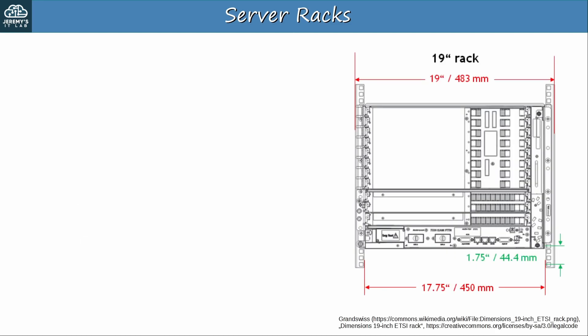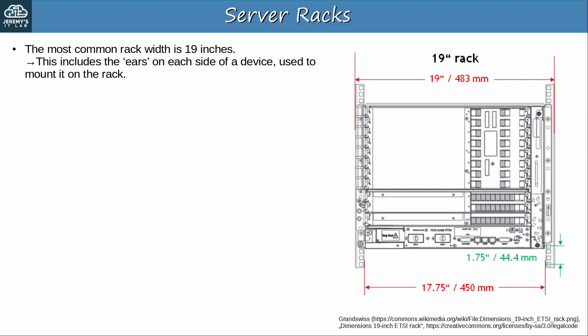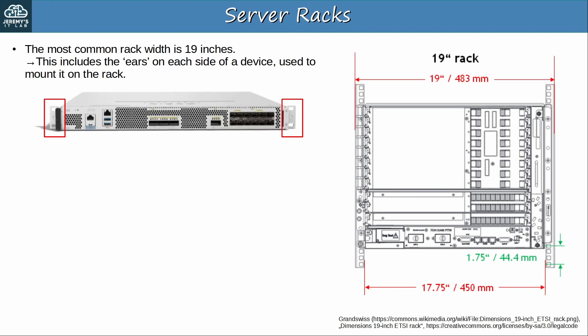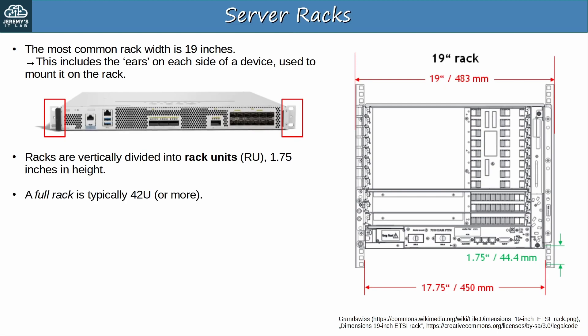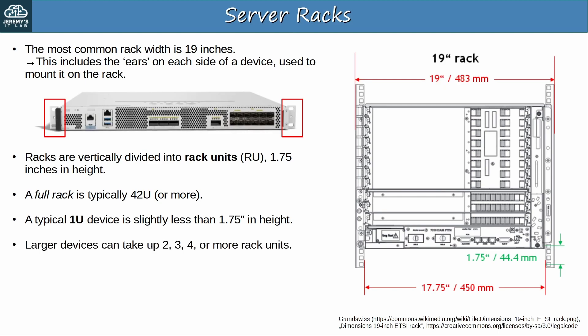Now let's look at the dimensions of a rack. The most common rack width is 19 inches, or 483mm. This includes the ears on each side of a device, used to mount it on the rack. Here's a Cisco switch — notice the ears on each side; that's how you mount the device on the rack. Racks are vertically divided into rack units, RU, each one 1.75 inches in height. A full rack is typically 42 rack units or more, but racks come in various sizes. Note that you might see a rack's height or a device's height written as RU, rack units, or just U, units. A typical 1U device is slightly less than 1.75 inches in height, so it fits within the 1 rack unit dimensions. Larger devices can take up 2, 3, 4 or more rack units.